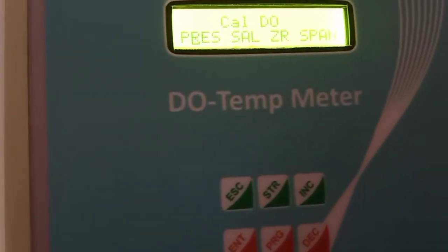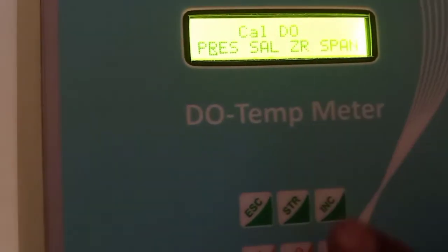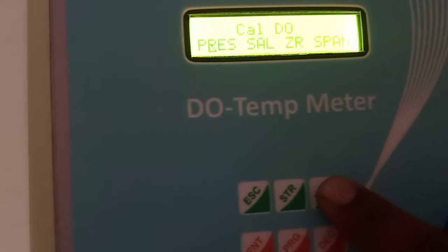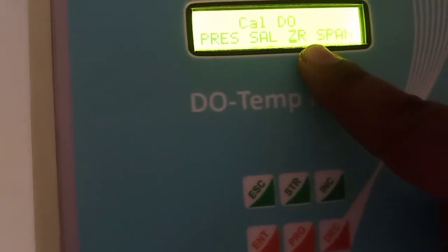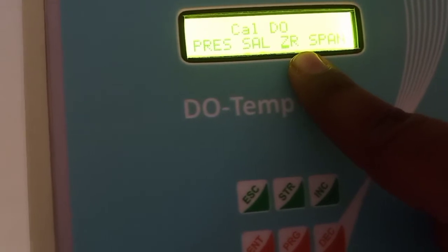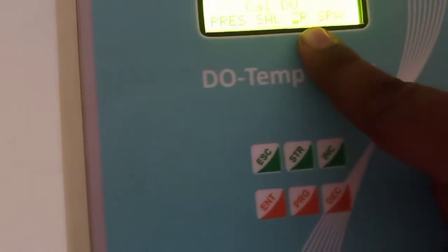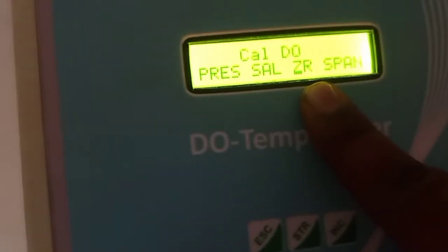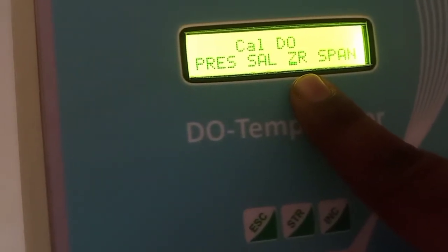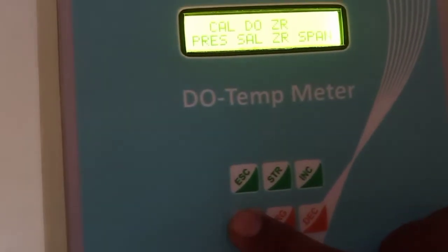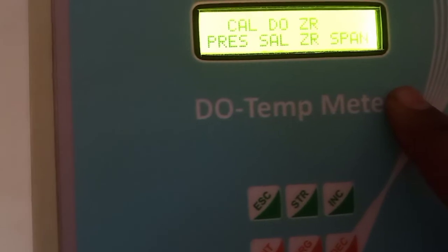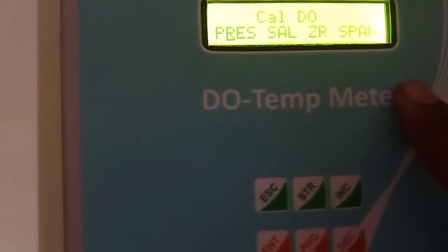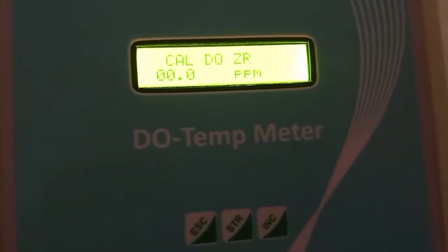After that, which do you want to calibrate, temperature or DO? Here we are going to calibrate DO, cal DO. So check the cursor. PRES stands for pressure adjustment, but we are not going to change the atmospheric pressure. So move the cursor toward 0 and press enter. Now ZR comes in the first row. Here ZR stands for 0.